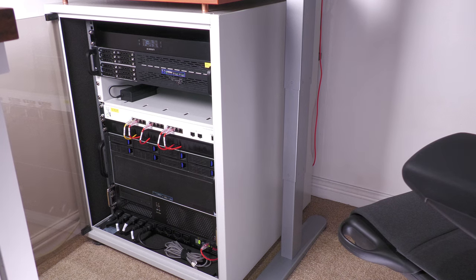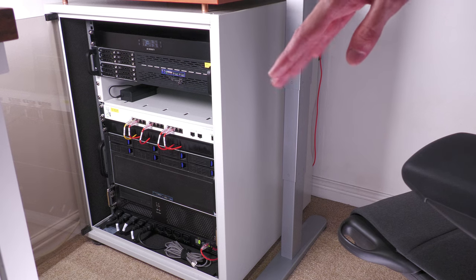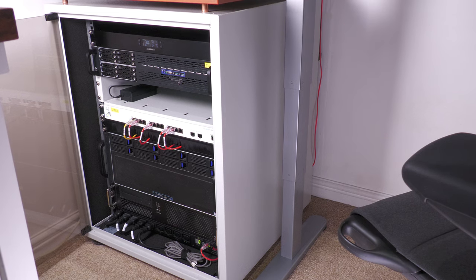So the problem is that when the rack gets too cool, if the fans do too good a job and cool it down, or the room's a little bit cold during the day, the rack will cool down enough that the fans will turn off. At that point, there's no cooling, the rack will start heating up again, and the fans then need to turn on again. And then you notice that cycling. In order to reduce the cycling, I ended up setting the buffer to 3, so it has to increase by 3 degrees for each step up in fan speed. And that's helped. But it then means that to actually reach fan speed 6, if the rack's really heating up, the rack has to heat up a fair bit before it reaches the maximum fan speed.